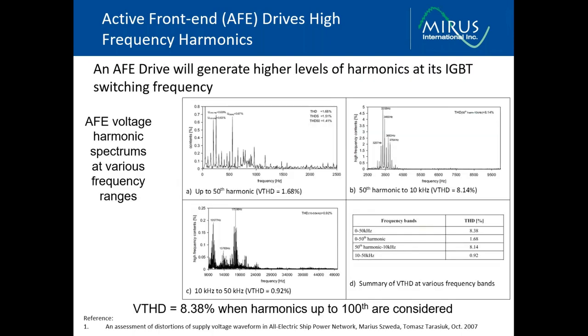And this next slide shows some measurements taken from another paper that was written, again, a marine application. In this paper, they were looking at the harmonics being generated over the full harmonic frequency, and they're measuring the voltage on the generators in the ship. When measuring up to the 50th harmonic, this is a 50 hertz system, so 50 times 50 is 2.5 kilohertz. So up to the 50th harmonic, the voltage distortion was only 1.68%, so well within the requirements of any of the standards, whether they're the electrical standards or the marine certifying standards.